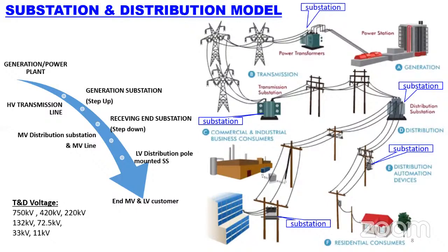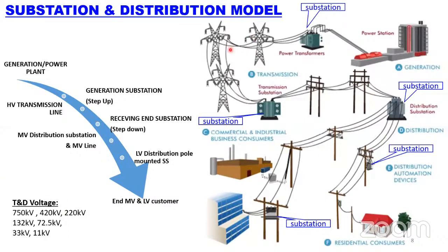After the transmission line, let me put my cursor so it will be clear. These are the transmission lines, traveling to the receiving substation. This is just the reverse of the generation station, meaning it will step down the voltage. Let's take the transmission happening at 765 kV, and after reaching this receiving end station, it will step down further to either 400 kV or 220 kV.